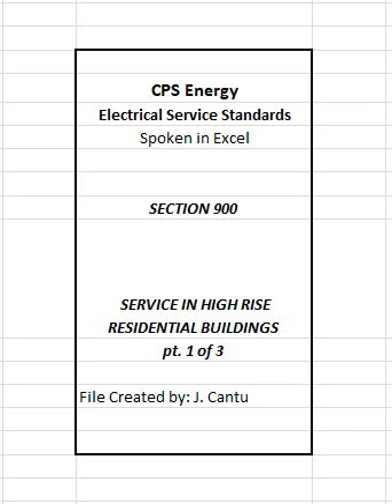903.1 Easements for CPS Energy equipment. Easements shall be as specified by CPS Energy and will be required for all CPS Energy equipment located outside and inside building. 903.2 Primary voltage duct line and conductors to CPS Energy equipment outside building. Customer shall furnish and install the underground duct line that is used to contain the primary voltage conductors from the CPS Energy distribution line to the primary 3-phase pad mount switchgear/transformer on customer's premises. Its installation shall be in accordance with Section 1000. CPS Energy will furnish, install, and maintain the primary voltage conductors to the primary 3-phase pad mount switchgear/transformer equipment.